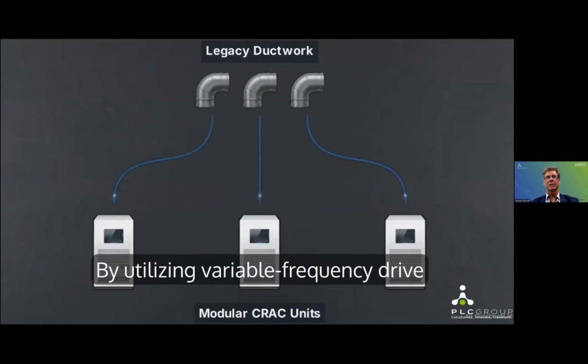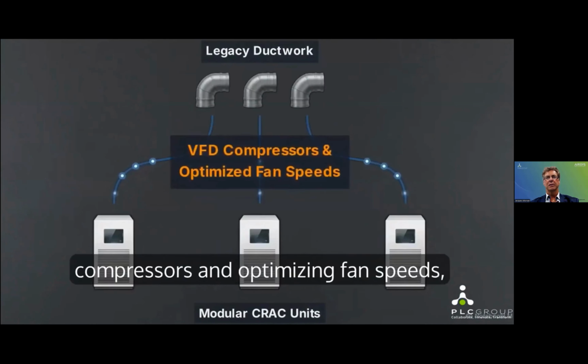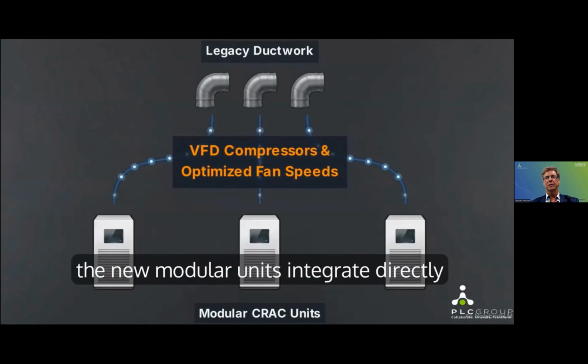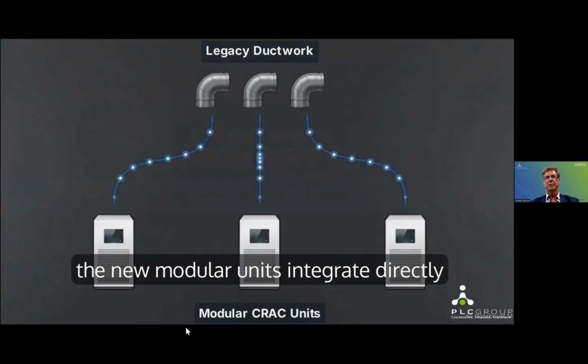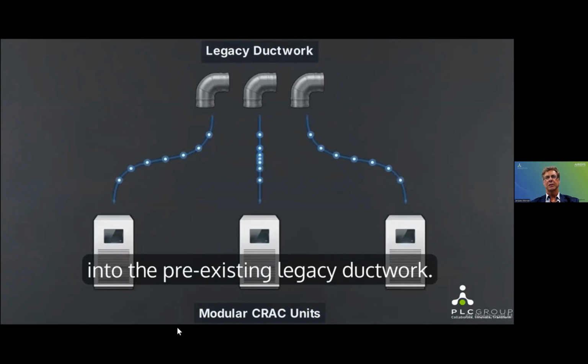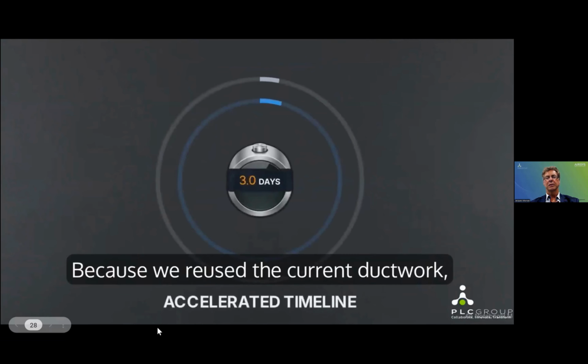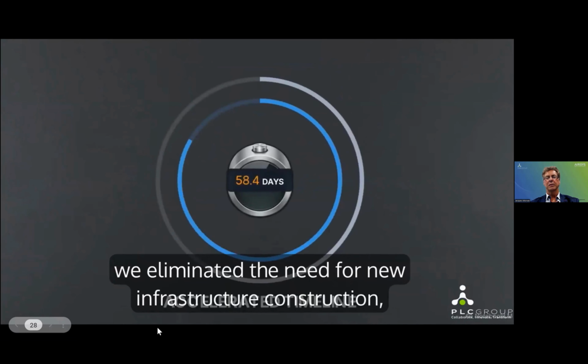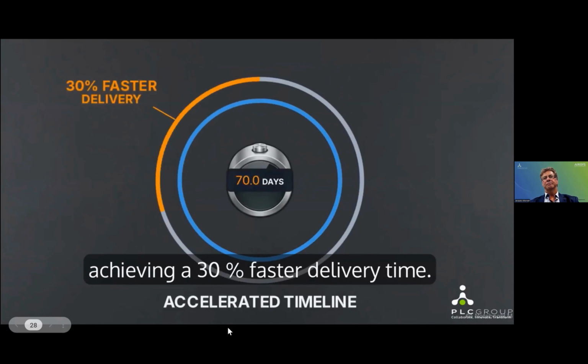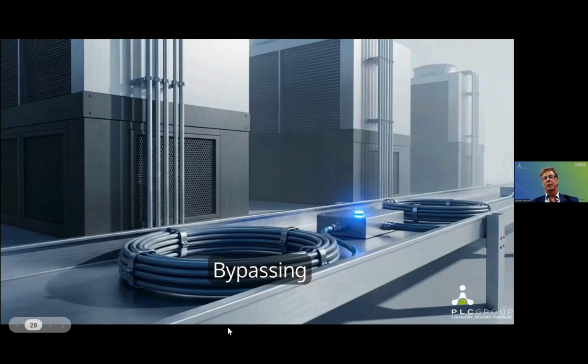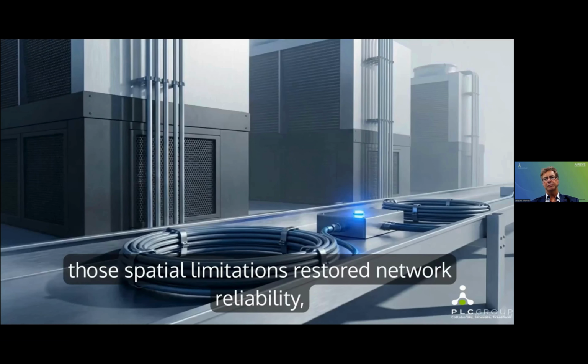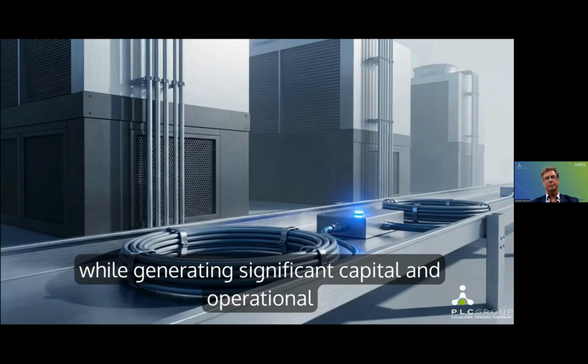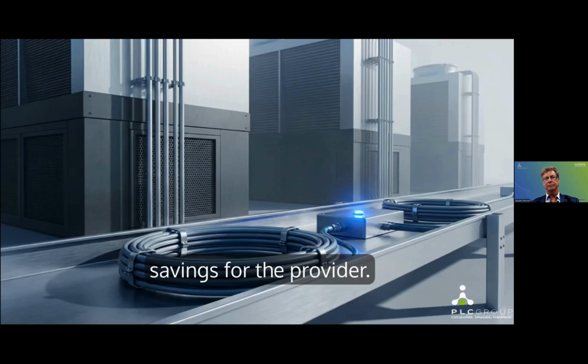By utilizing variable frequency drive compressors and optimizing fan speeds, the new modular units integrate directly into the pre-existing legacy ductwork. Because we reused the current ductwork, we eliminated the need for new infrastructure construction, achieving a 30% faster delivery time. Bypassing those spatial limitations restored network reliability while generating significant capital and operational savings for the provider.